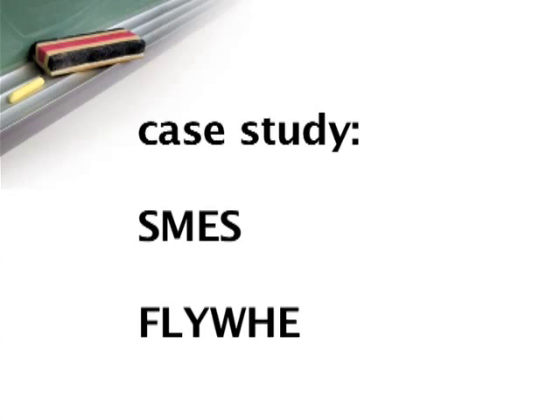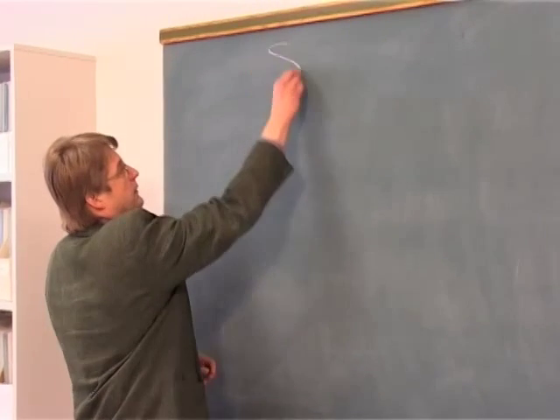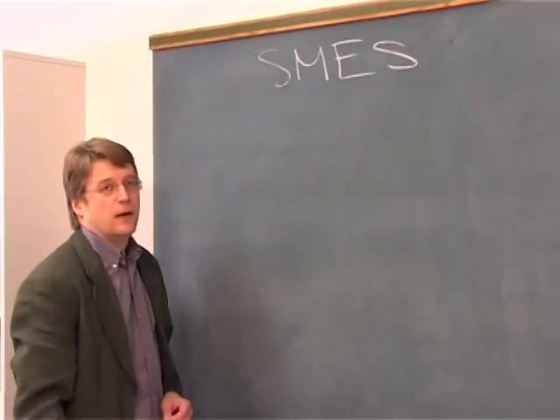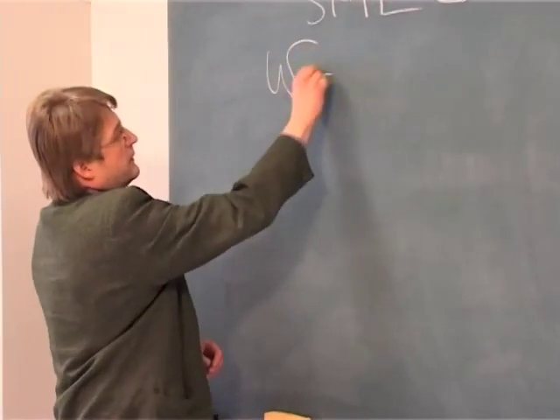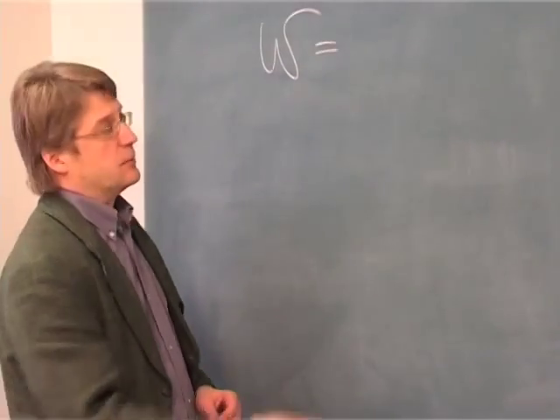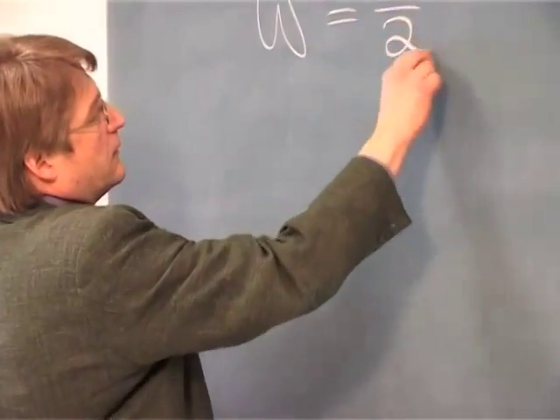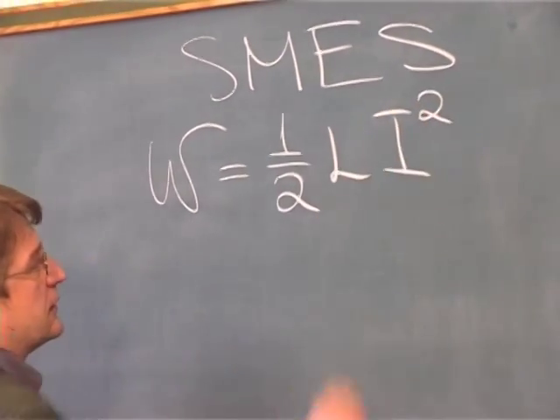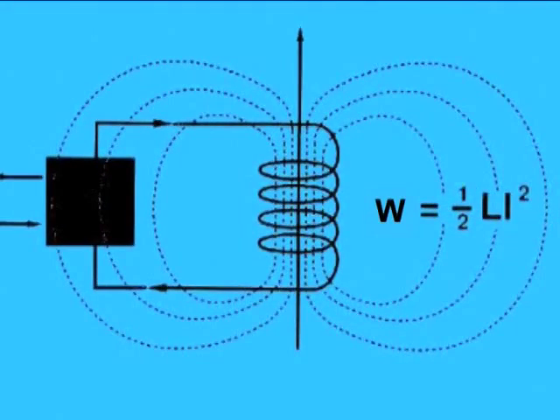As I said, we have two ways to store energy. And the first one is SMES. And the energy which we can store can be given with a quite simple equation: 0.5 times inductance times the current squared. So this L means the inductance of the coil, and I is the coil current.